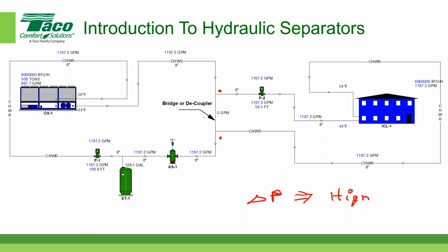So let's say that the pressure drop across the bridge was 20 feet. That means that the resistance of the secondary circuit would also have to be 20 feet. So whatever flow would be necessary to have the secondary circuit have a 20-foot pressure drop, that's the flow you would get as a consequence of having a pressure drop across the bridge of 20 feet. So it would induce flow in the secondary circuit, and if it's a true hydraulic separator, we don't want that to happen. So we never want that pressure to be high.